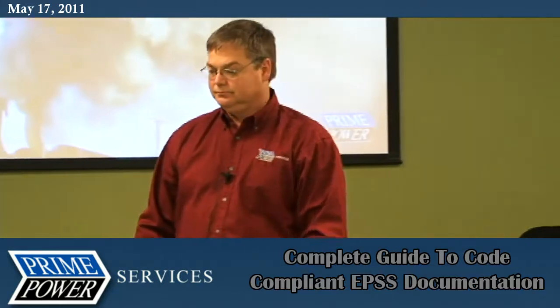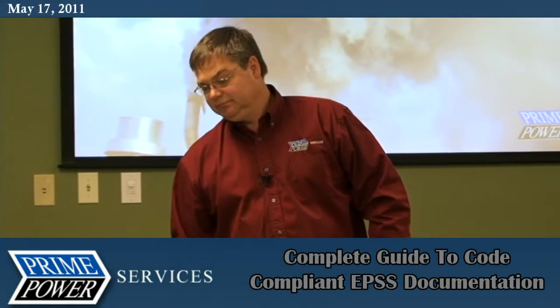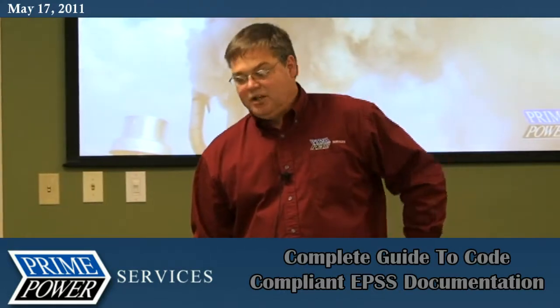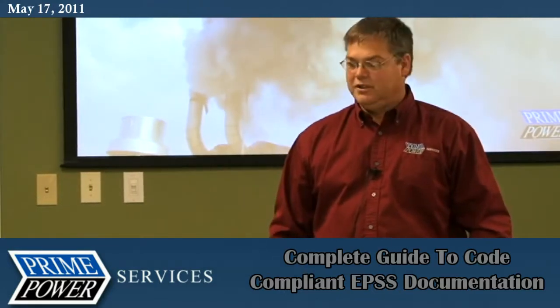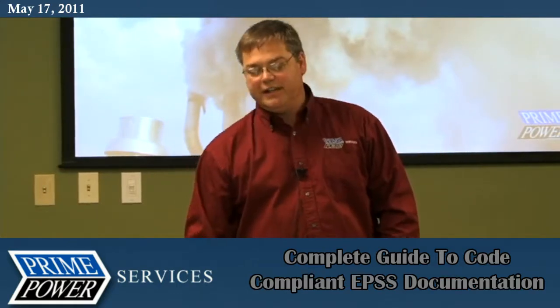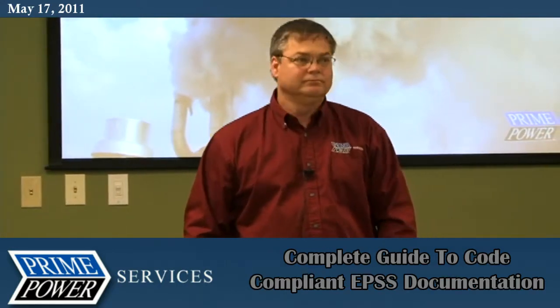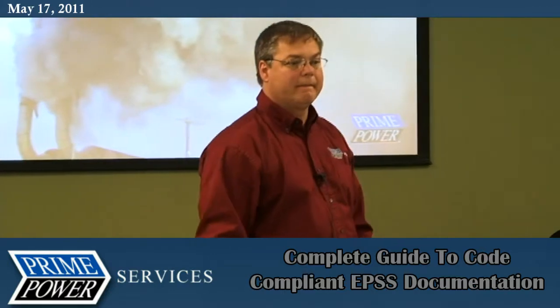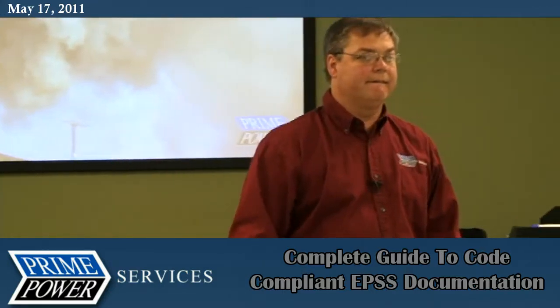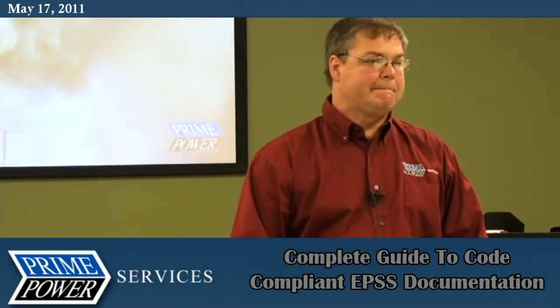Right. And in NFPA 110, on electric fire pumps, does it say how long? No, there's no time limit on electric fire pumps. It's a churn test for the motor. I thought it said something about running it 30 minutes under load after it reaches running temperature.